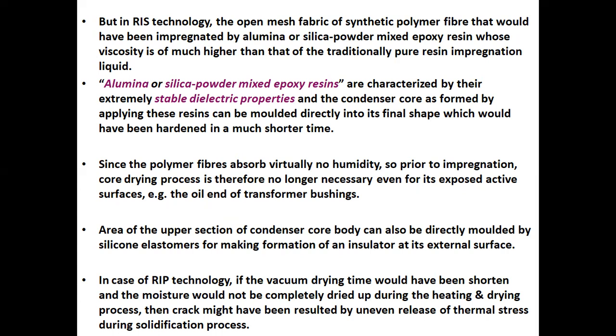Alumina or silica powder mixed epoxy resins are characterized by their extremely stable dielectric properties, and the condenser core formed by applying these resins can be molded directly into its final shape, which hardens in a much shorter time. This is the advantage of using silica powder or alumina mixed epoxy resins.